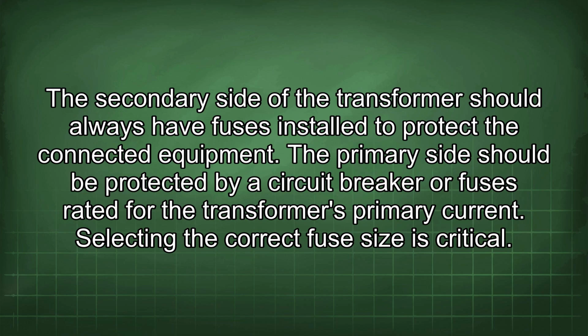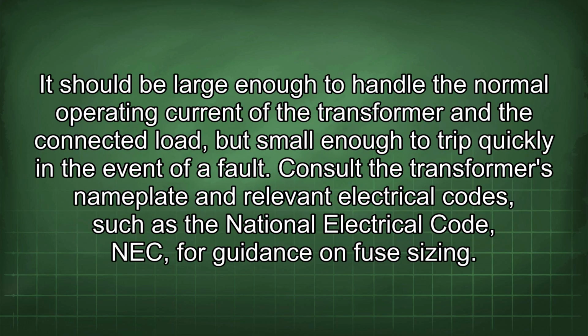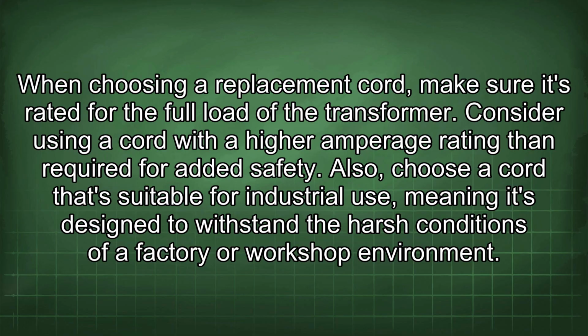Selecting the correct fuse size is critical. It should be large enough to handle the normal operating current of the transformer and the connected load, but small enough to trip quickly in the event of a fault. Consult the transformer's nameplate and relevant electrical codes such as the National Electrical Code, NEC, for guidance on fuse sizing. When choosing a replacement cord, make sure it's rated for the full load of the transformer. Consider using a cord with a higher amperage rating than required for added safety.